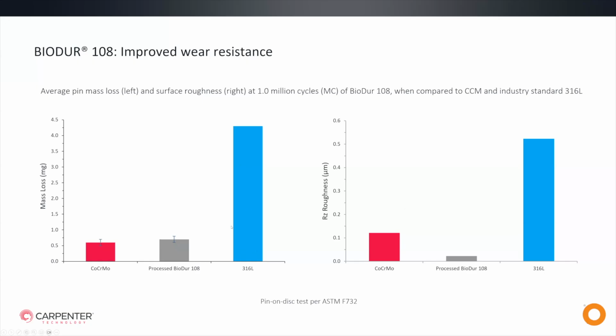As you see on these slides here, in the actual results that we're sharing, BioDur 108 demonstrated comparable mass loss and surface roughness to the cobalt-chrome molybdenum, even under a rather aggressive 1 million cycles on a pin-on-disc test. So this means that it may be a viable alternative to cobalt-chrome.